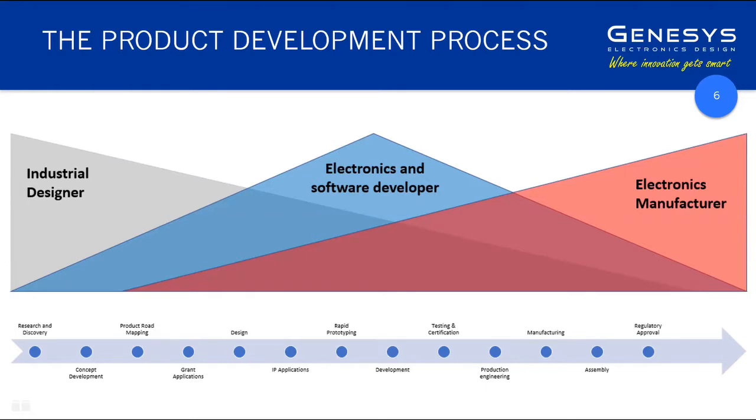Yeah, and look, I'm just aware of bandying around this word ISO 13485, just for anybody who missed the earlier webinars. That is a quality management standard that any company that's marketing or was the official owner, or what they call a product sponsor, of a medical device must have in place. And you made the comment that ideally their suppliers, the designers and the manufacturers, would also have 13485. So you, as a product developer, need to be a 13485 certified business yourself. But ideally, if you're an industrial designer, your electronics designer and your electronics manufacturer will also be 13485 certified, it just makes the whole process easier, doesn't it?